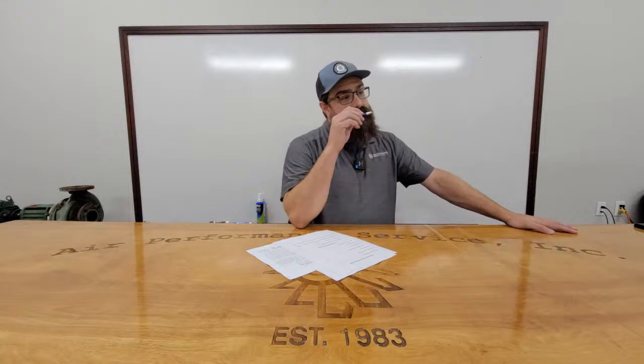But there are three ways to control a valve actuator. Like I said, it would either be on off, modulating with like a 0 to 10, or floating with a voltage to open, voltage to close type deal. Didn't they call those three? There was some term, because I took the Belimo online school. They talked about the floating, your conventional on off. I don't remember what Belimo calls it. They have a term, three position or something. Well, it wouldn't be three position. It's the dash 3s on Belimo. Their part numbers are like, if you have an AMB dash 3, that denotes the torque, the frame size, and the voltage, and then dash 3 would mean the three wire: power open, common, power closed. But it just depends. Different brands have different terminologies for part numbers. But maybe one day we'll do another class on valves where Casey doesn't just tear everything apart.